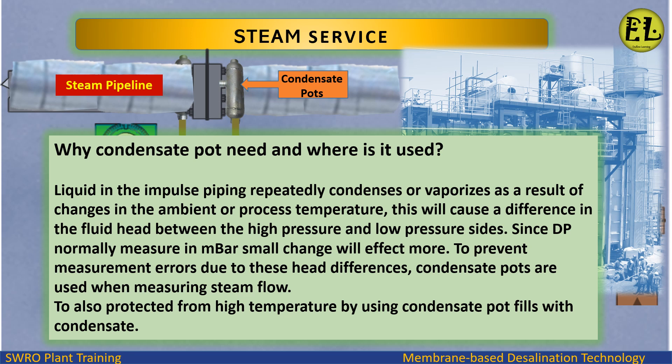Why is a condensate pot needed and where is it used? Liquid in the impulse piping repeatedly condenses or vaporizes as a result of changes in the ambient or process temperature. This causes a difference in the fluid head between the high pressure and low pressure sides. Since DP is normally measured in millibar, small changes will affect the reading more. To prevent measurement errors due to these head differences, condensate pots are used when measuring steam flow.